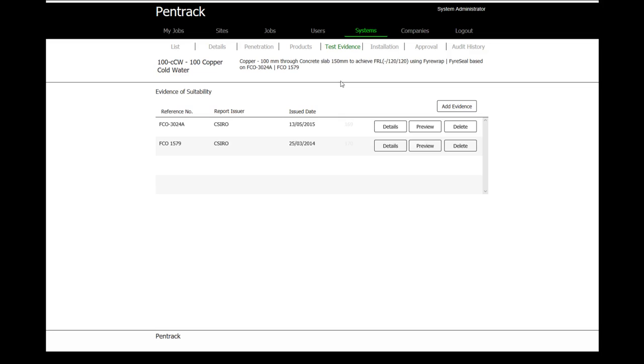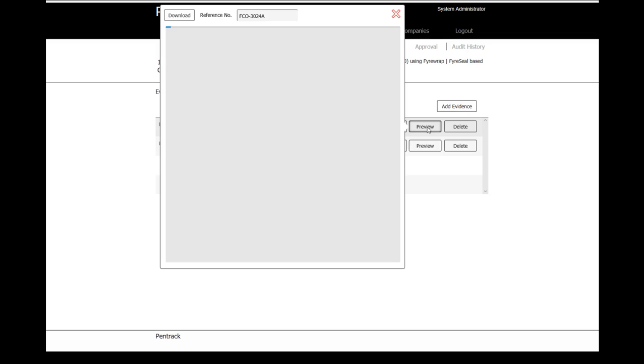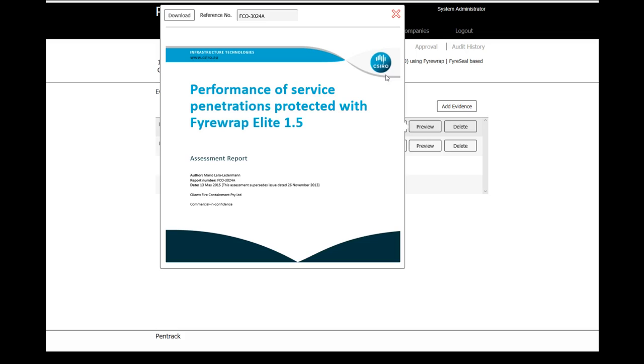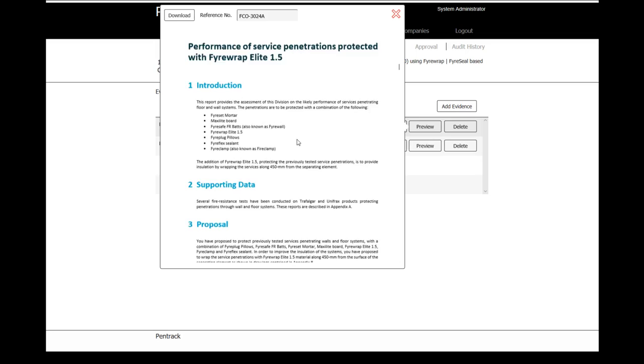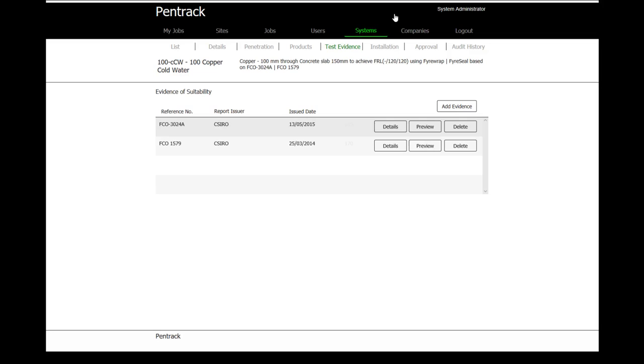In terms of test evidence, when you're going through and putting a system into a building, you need to be able to show on what basis that system can be used. In this case, we've got a couple of reports here from the CSIRO that actually support the use of those products for the intended purpose. We can preview that evidence and I'll just bring up a report. As we can see here, they've done a performance of service for the use of the Fyrewrap Elite 1.5, and there's an assessment report that provides evidence for using that particular system. Because we're using two products, we have two lots of evidence that have been captured.